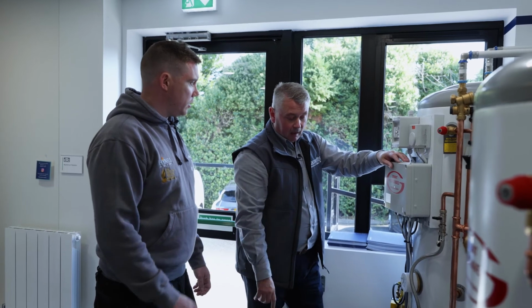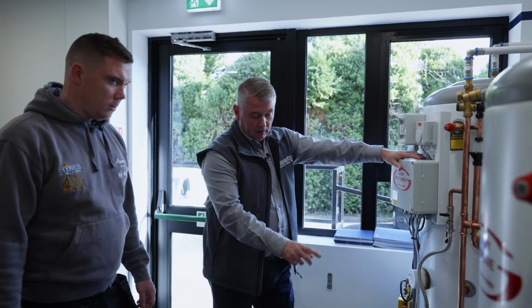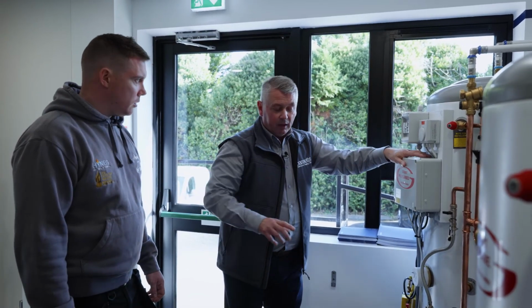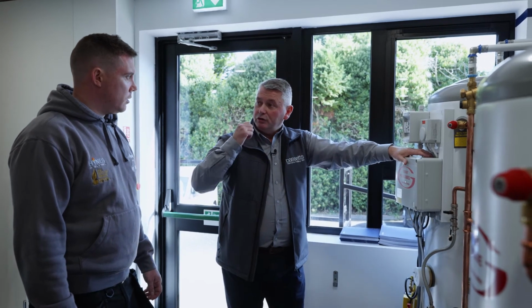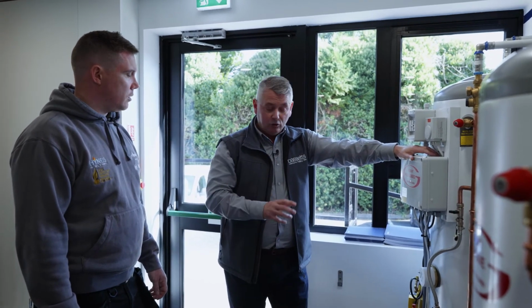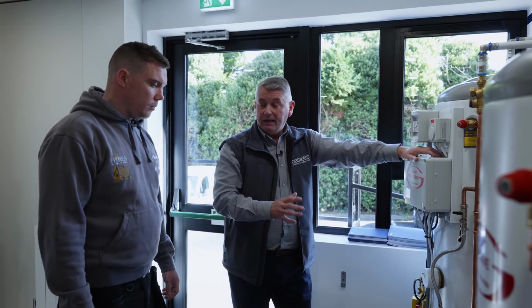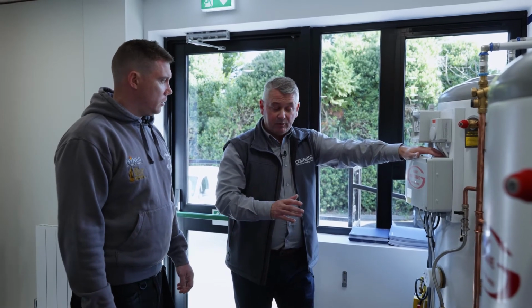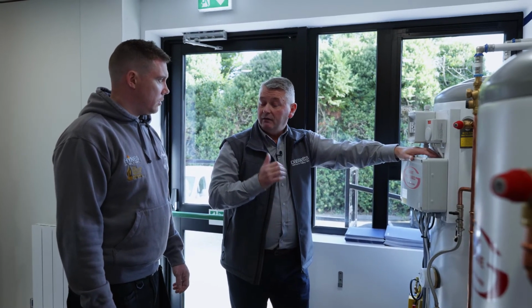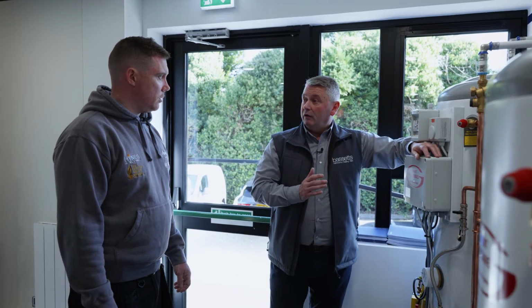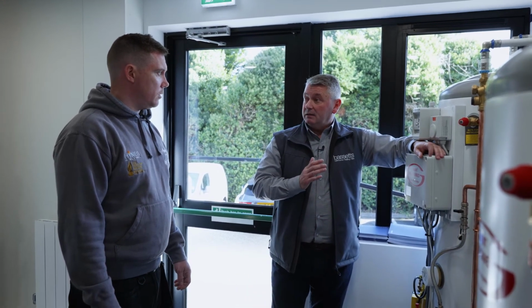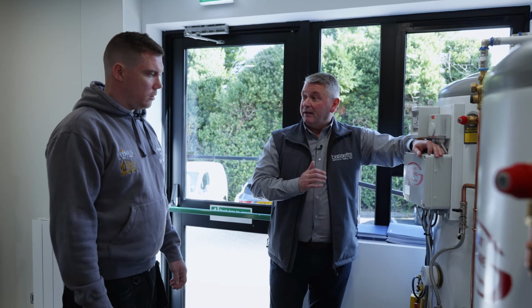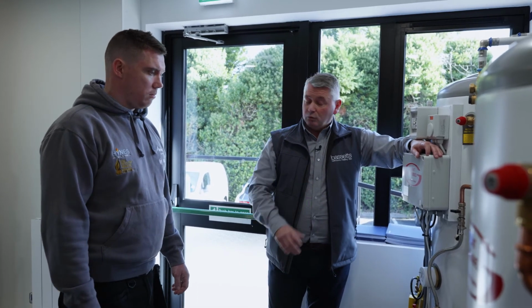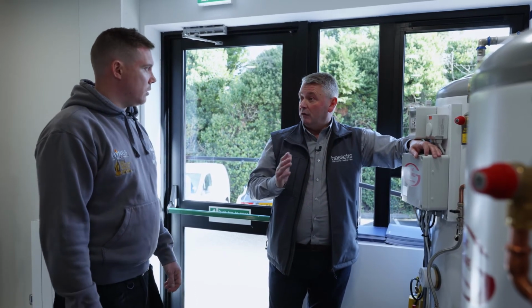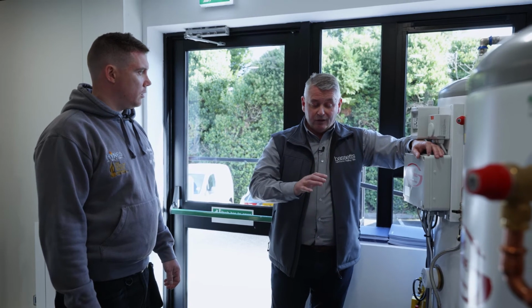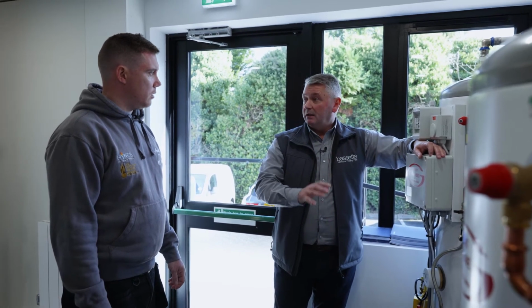Is there a buffer tank with this? There's a 30-litre buffer we've installed here. There's a minimum volume for the system, so as to stop the heat pump cycling, there'll be a minimum volume of 80 litres in the system. This is to prevent the cycling, the on-off. Heat pumps work on an off-on cycle with a life expectancy of 75,000 starts for the compressor, so we want to prevent the off-on as often as possible, making sure there's adequate volume of water in the system to prevent that.